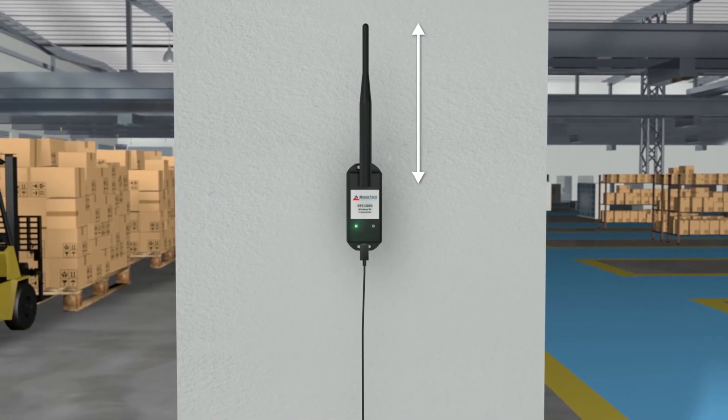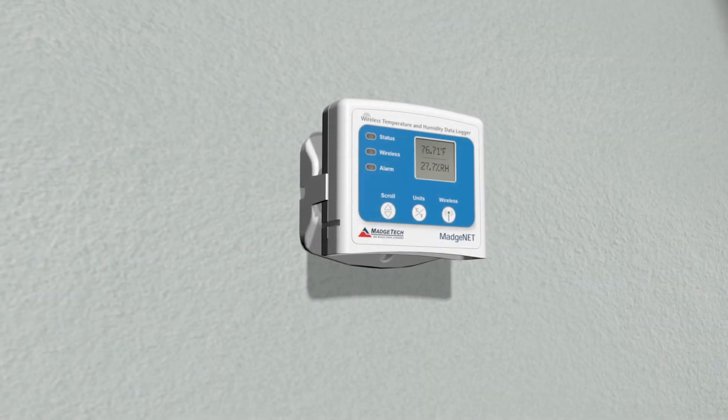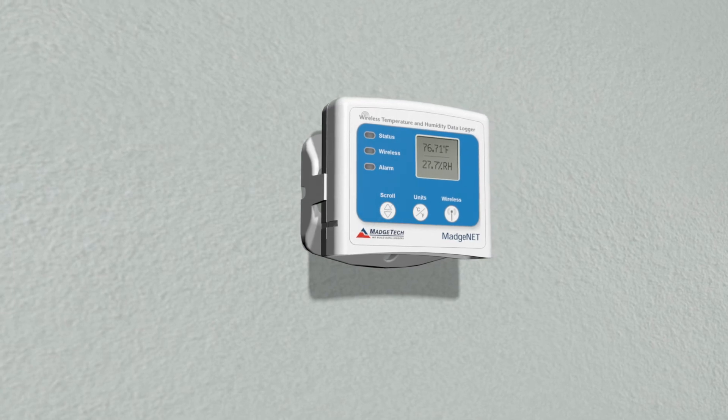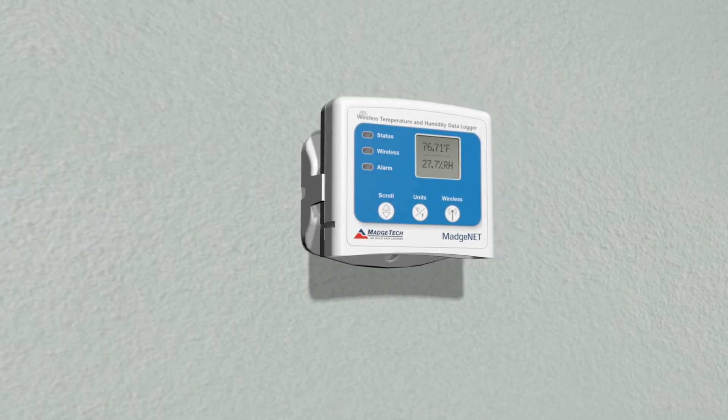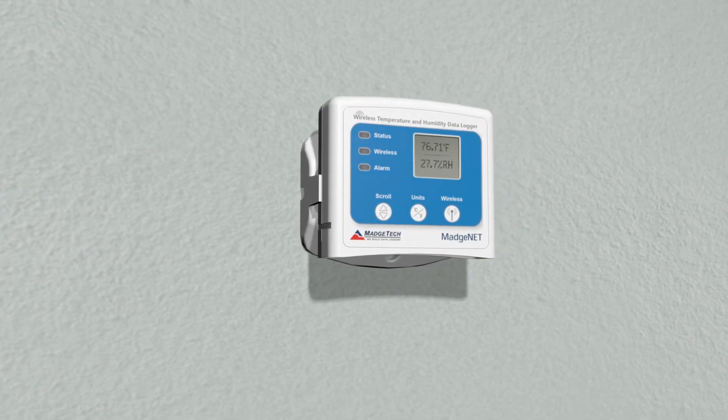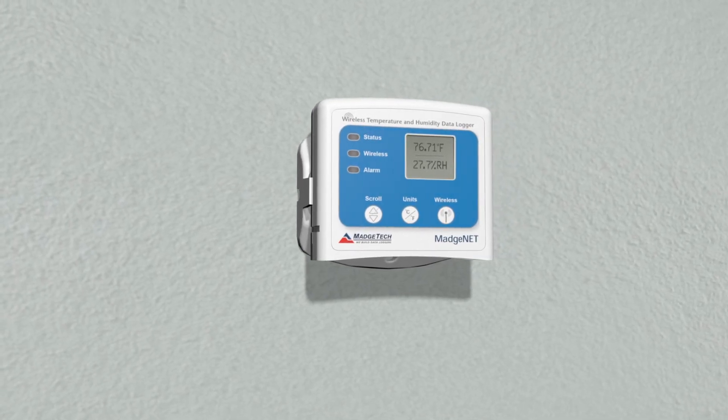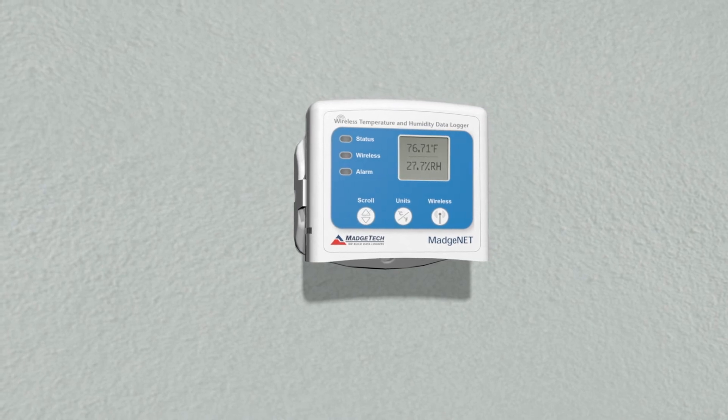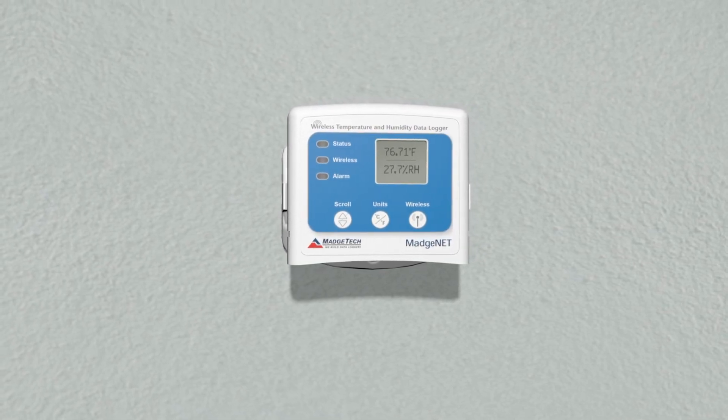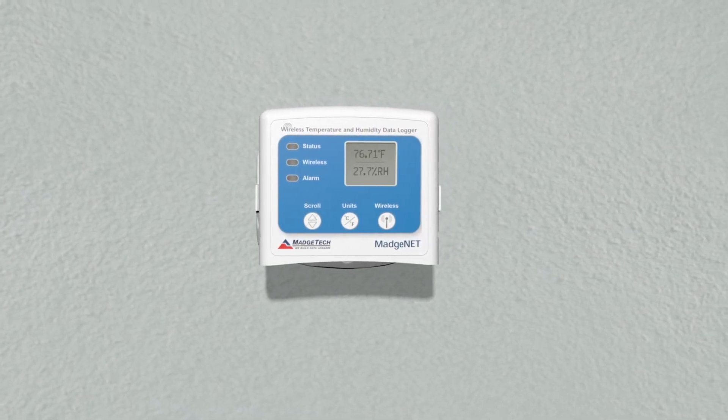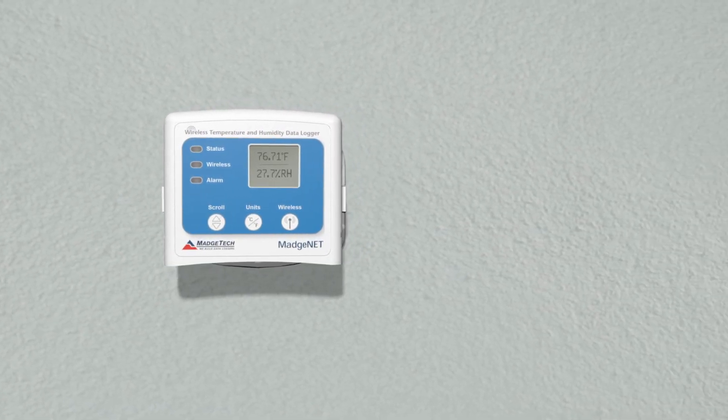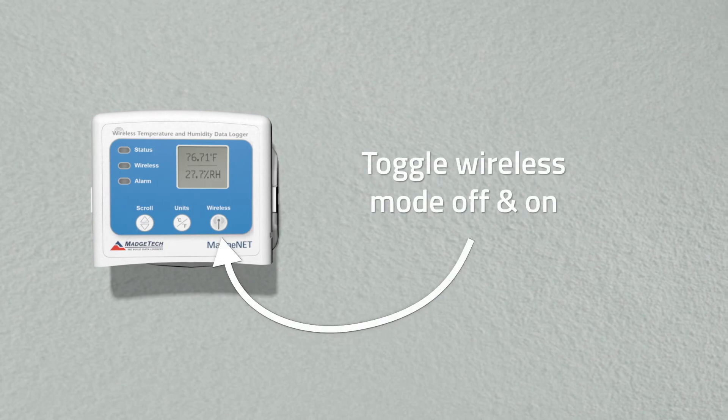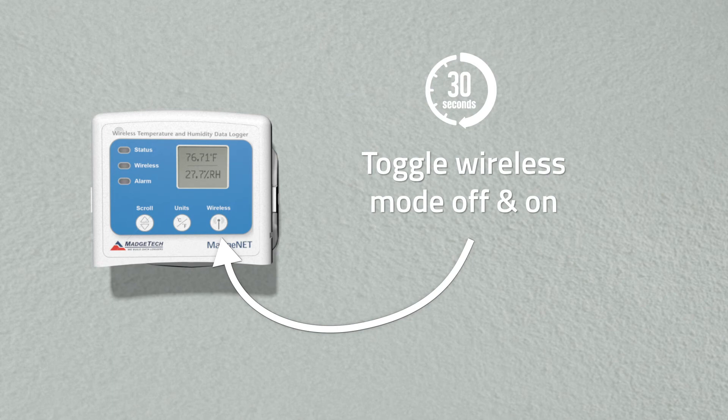Once transceivers have been placed, we now need to ensure the loggers are communicating with them. The logger will only connect to a new RFC-1000 or cloud relay after losing connection. If new repeaters or relays have been added to the network, turn off wireless mode on your data logger, wait 30 seconds, and then turn it back on. The loggers should now connect to the new repeater or relay with the best signal.